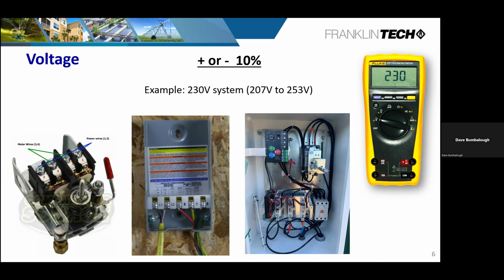So that would get you in trouble if you were to hook that up to a 480 volt system, because in most cases those run in the 490s to almost 500 range now. And if they have any kind of spikes or transients rolling down the line, that could cause wire burnout. So you want to be very careful there. That extra tolerance is built in for those issues, transients, and any kind of switching action that may happen on the main lines that can cause spikes. The wire threshold is very crucial. As we go through this presentation, I'll show you how to check for that and also some of the meters to use in those cases to make sure that wire hasn't been compromised.